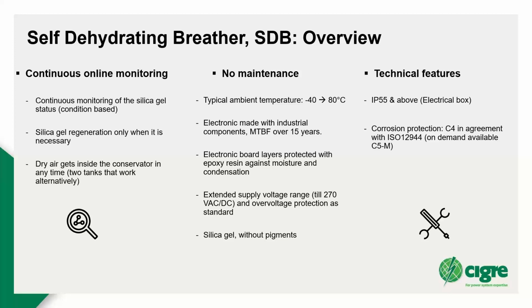There are certain benefits. Continuous online monitoring is one, where you get to know the status of the silica gel, and the silica gel is automatically regenerated when necessary. Because we have 2 tanks which work alternatively, you have dry air going inside the conservator at any point of time. Typically these work well from -40 to 80 degrees.